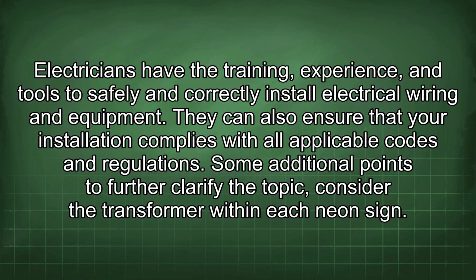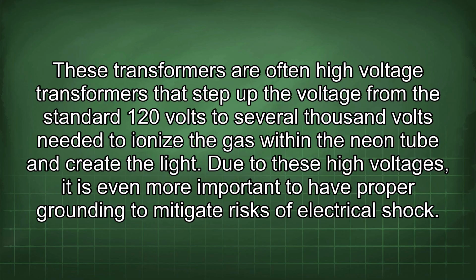Some additional points to further clarify the topic: consider the transformer within each neon sign. These transformers are often high voltage transformers that step up the voltage from the standard 120 volts to several thousand volts needed to ionize the gas within the neon tube and create the light. Due to these high voltages, it is even more important to have proper grounding to mitigate risks of electrical shock.